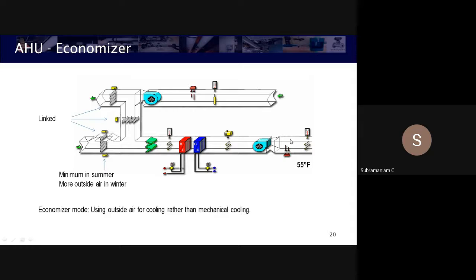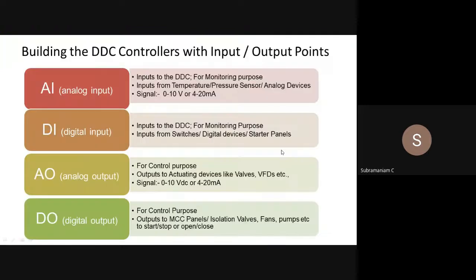I can circulate this air to the room and have a comfort condition of 75 degrees Fahrenheit inside. That means I am not spending energy. What I am doing is just sending outside air. But for that, we have to have motorized dampers, an enthalpy sensor or dry bulb based economizer, and have this exhaust fan, fresh air fan, supply fan, return fan, and accordingly modulate all this and then supply the air. So these kinds of things will come on the AHU controls also.